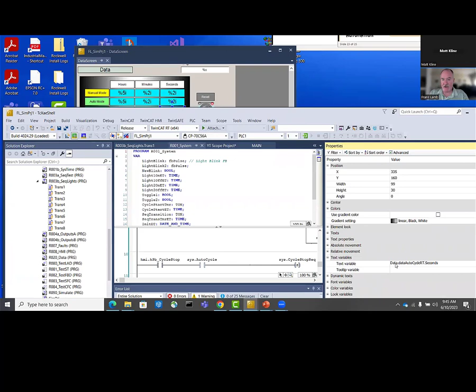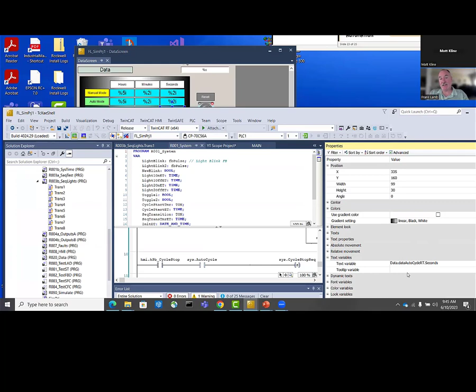For instance, this one here, this 5 is the number of characters that would show up here. It is in integer format. This one here is in floating point format, 3 and then 1 space, and then I forget what the percent is. I'd have to look that up again, but I believe that just means it's a variable, right? It's assigned to, let's click on one of them. Right, it is a text variable. So this is assigned to data tag, data autocycle RT, and this is a UDT. Actually, like I said, they call them DUTs here, and then seconds. So to link to this, this is just like a UDT in Allen Bradley.